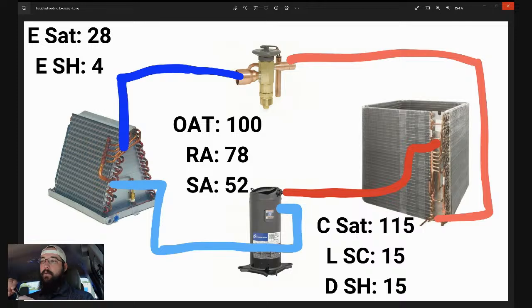Bypassing the evaporator. Okay, so in that particular case, one of two options could be that maybe a bracket rusted out on the evaporator and allowed the evaporator to sag because of an old rusty bracket, so now we're bypassing around the coil. The second alternative would be the cover plates on the end of the evaporator. Maybe it's just a really old system, or rusted out so badly that it allows air to go around it. Maybe a couple of screws, or vibration of the unit, maybe it's got a fan balance issue, and it caused the screw to back out enough to allow that cover plate to let air bypass. That could be a real alternative.